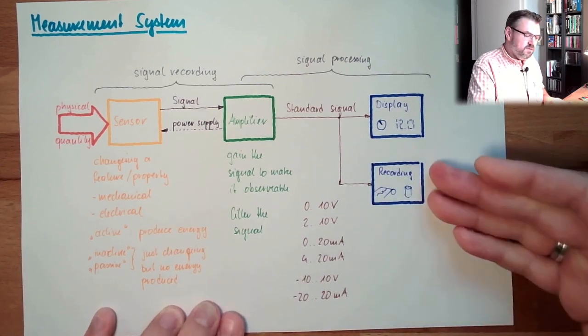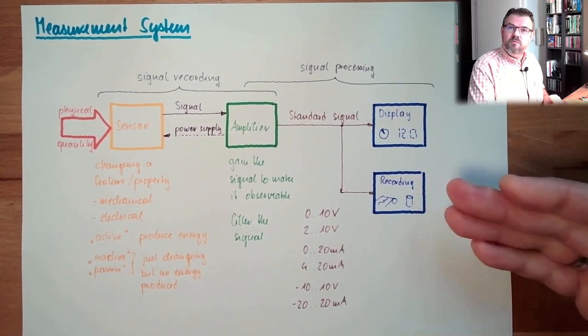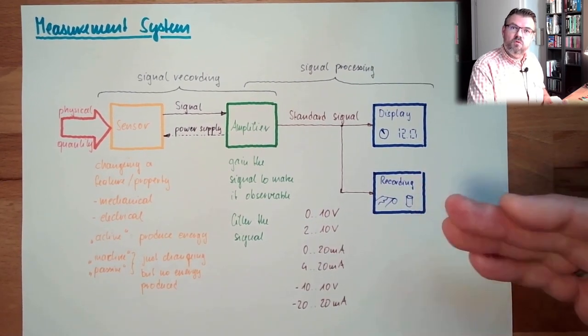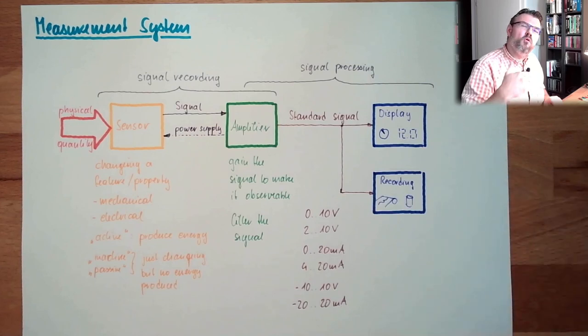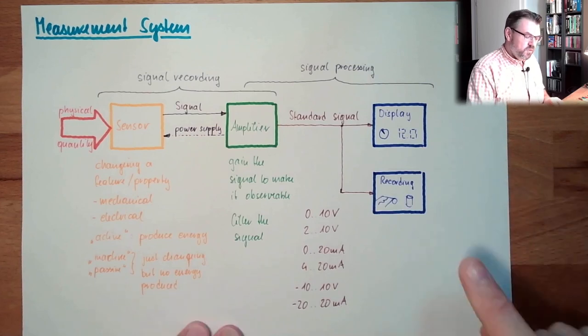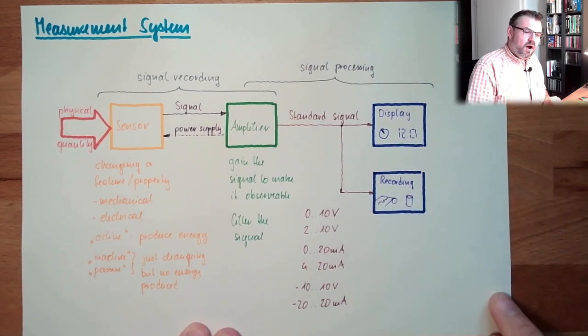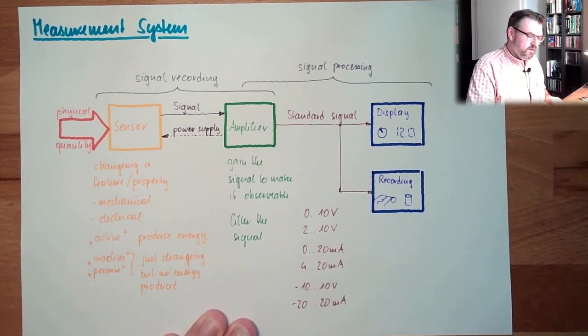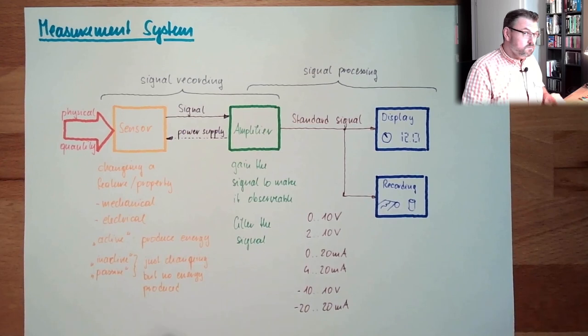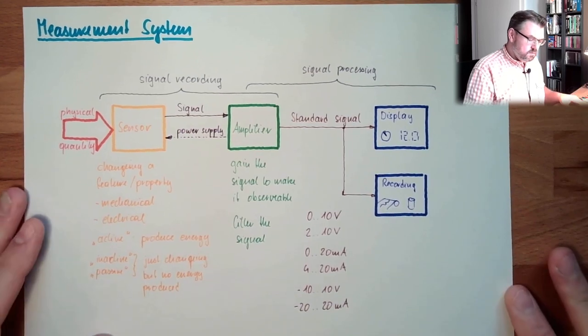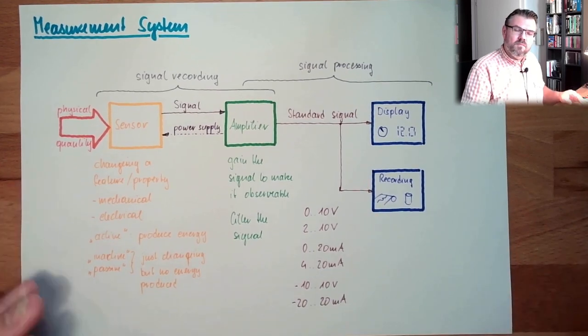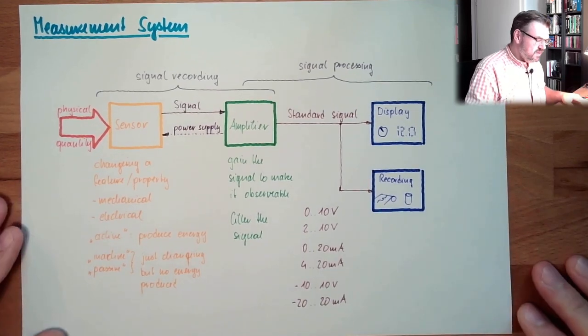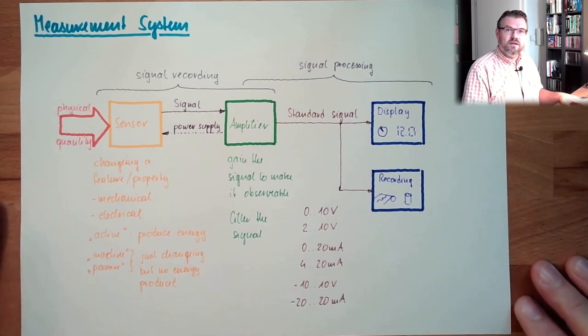These are typical standard signals — Normsignale. Usually you can buy a measurement device with such output. You buy, say, a temperature measurement from minus 40 degrees Celsius to 150 degrees Celsius, and it outputs 4 to 20 milliamps. Then 4 milliamps would be minus 40 degrees Celsius, 20 milliamps would be 150 degrees Celsius, and it is scaled accordingly.